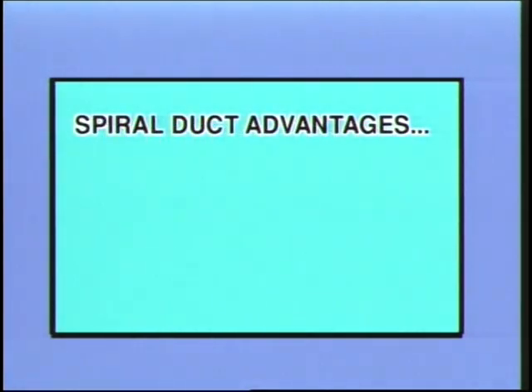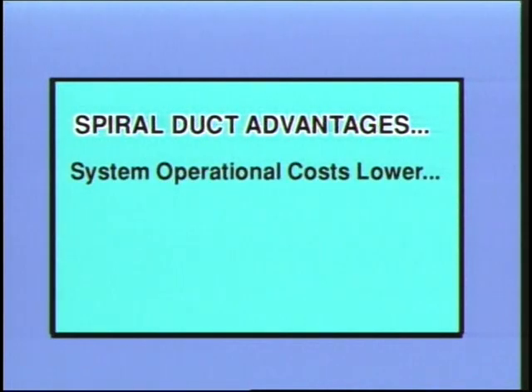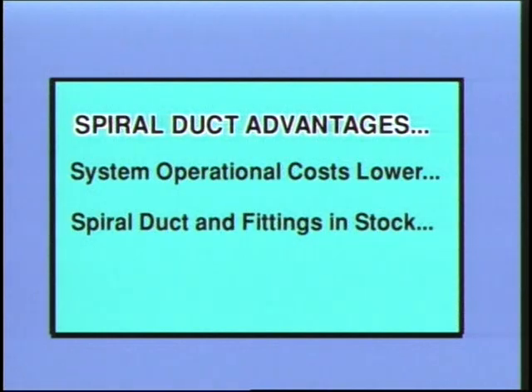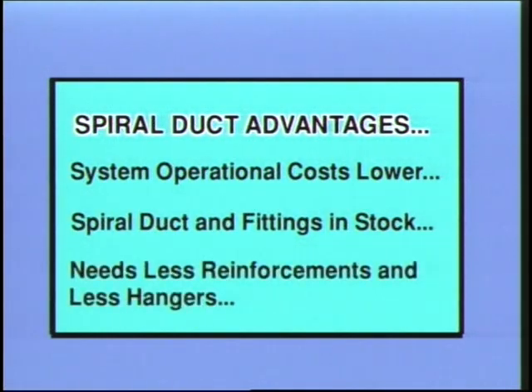Other spiral duct advantages when used for HVAC system ductwork are ongoing duct system operational cost savings, as shown by examples in the Designer's Guide, and prompt delivery, as spiral duct and fittings generally are stock items. Round spiral ducts need less reinforcement and fewer hangers because they're lighter in weight.